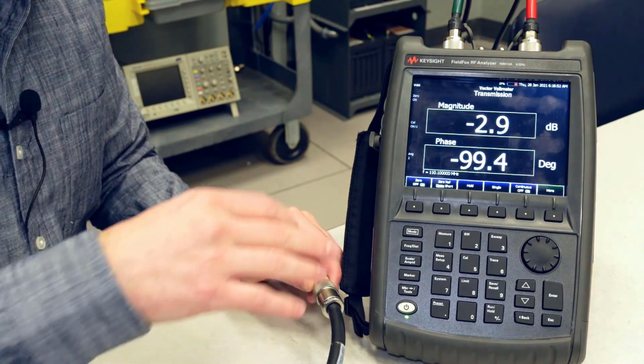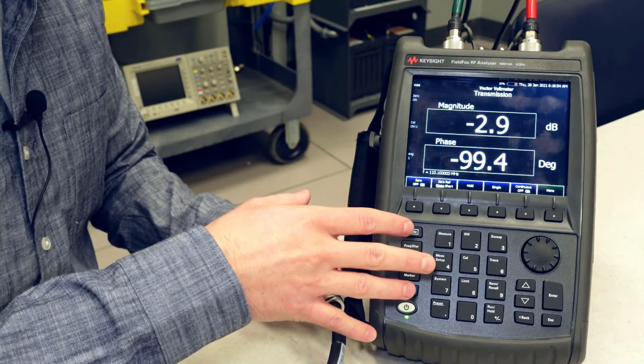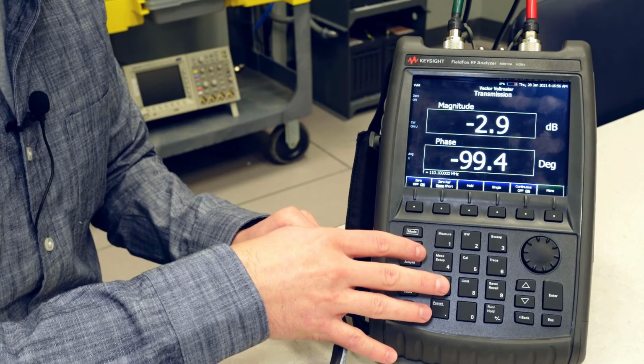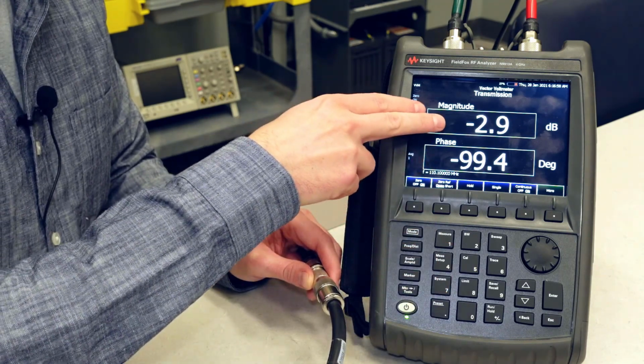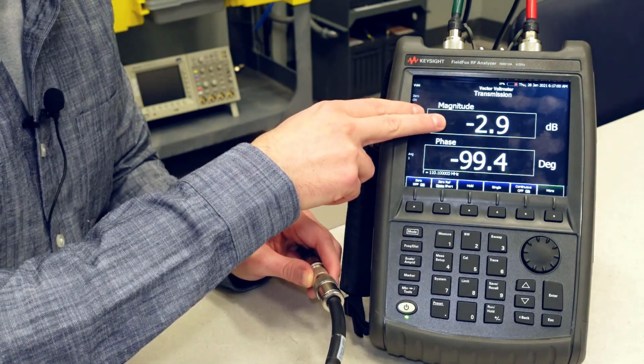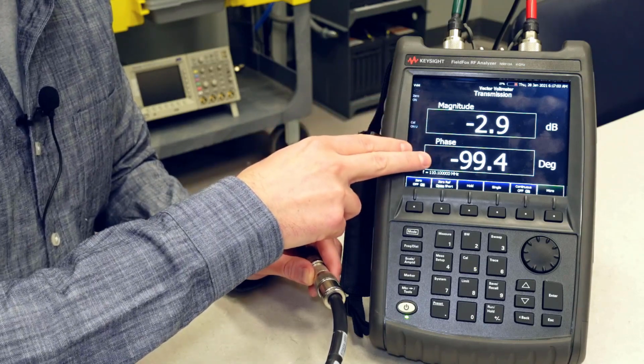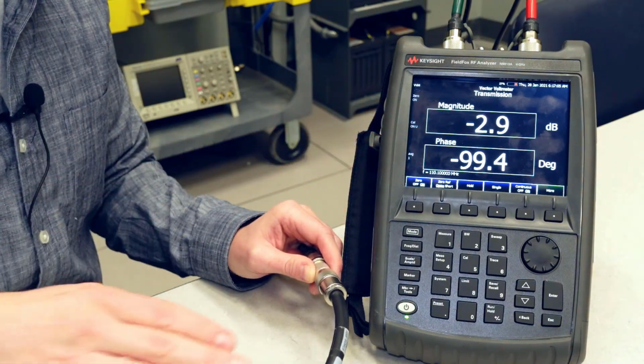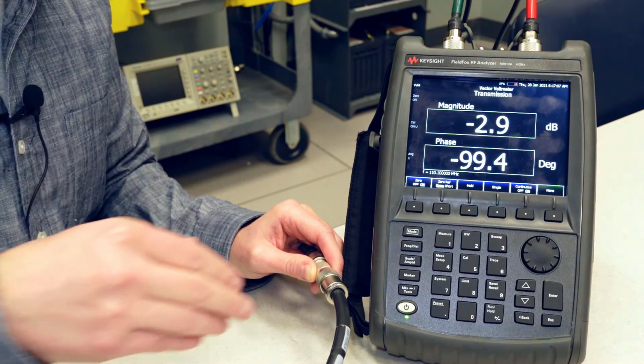And now you can see with very minimal input on the FieldFox, we were able to set this thing up and get pretty much the same results we got on the network analyzer mode, a negative 2.9 dB and a negative 99.4 degrees for this device under test.